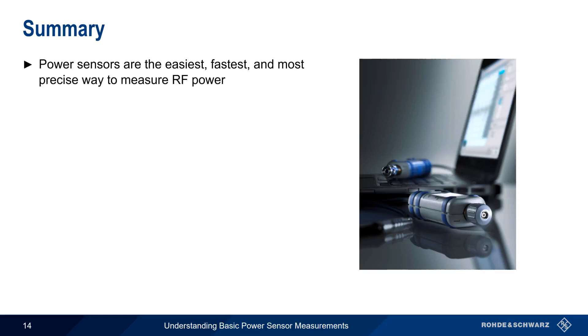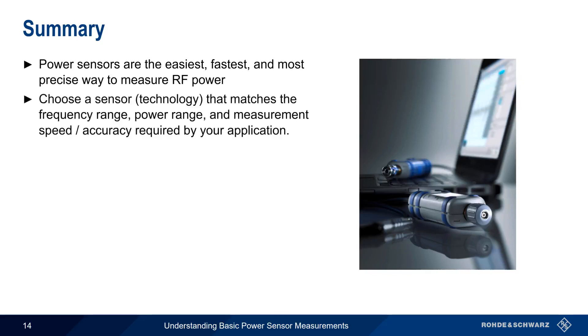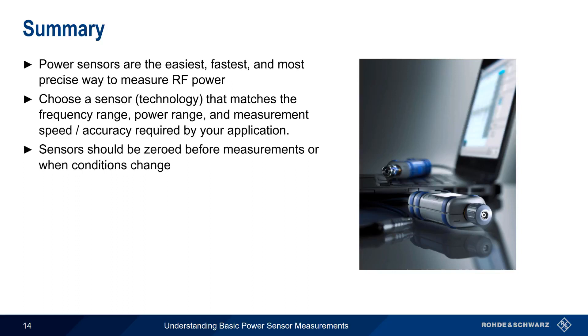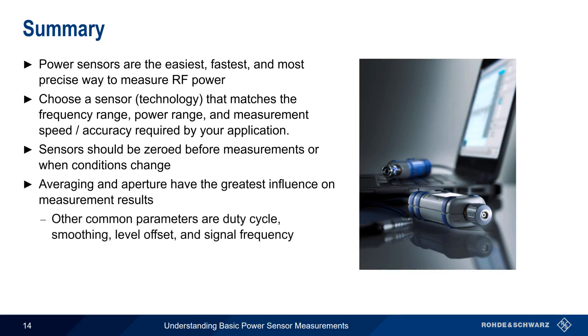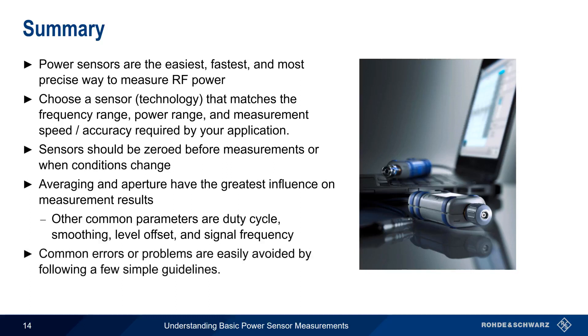In summary, power sensors are the fastest, easiest, and most precise way to measure RF power. When making RF power measurements, it's important to choose a sensor or sensor technology that matches the frequency range, power range, and measurement speed and accuracy needed by your application. Zeroing the sensor before use, or when conditions change, is always a good idea. Two parameters — aperture and average count — can have a significant impact on results. You may also need to adjust duty cycle for pulse signals, smoothing for signals that change sporadically, level offset when using attenuation, and signal frequency when the measured power is concentrated around a single frequency. It's easy to avoid the most common errors by following a few simple guidelines. This concludes our presentation: Understanding Basic Power Sensor Measurements. Thanks for watching.